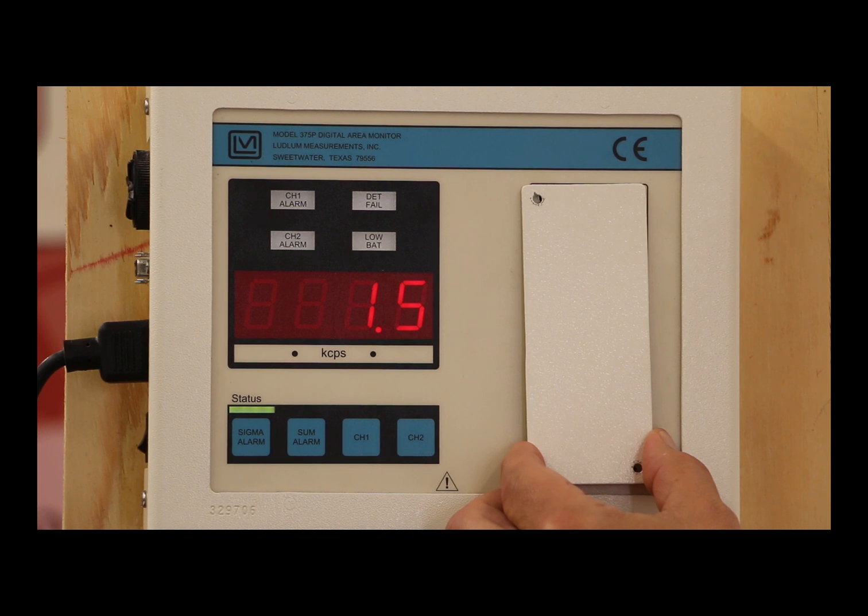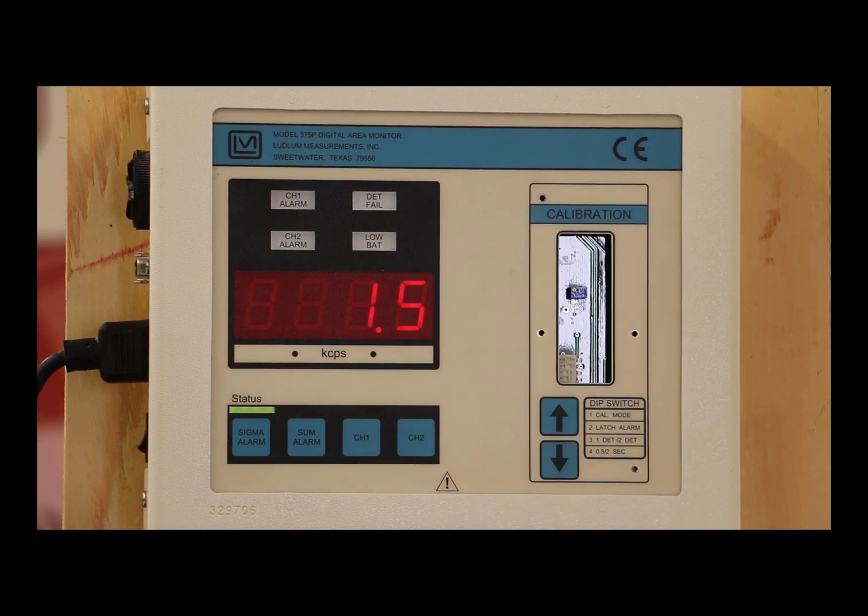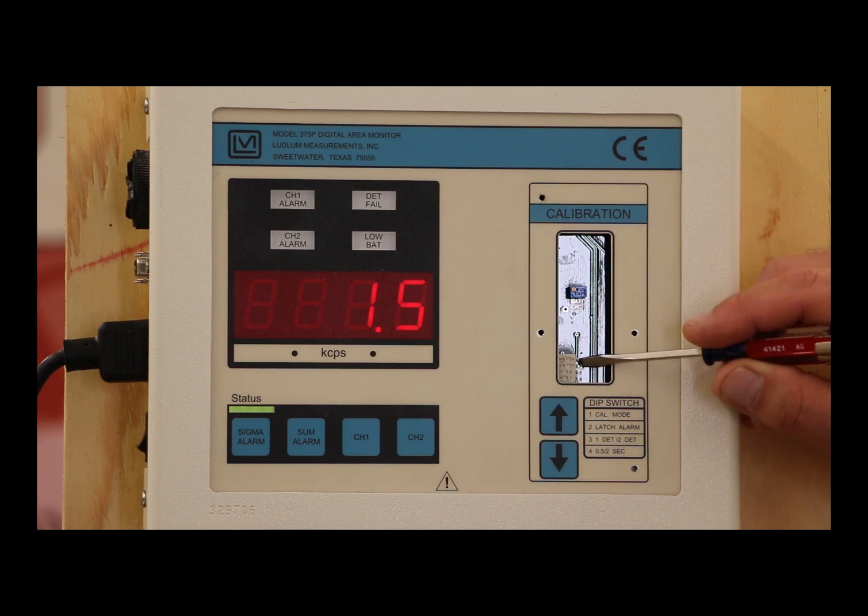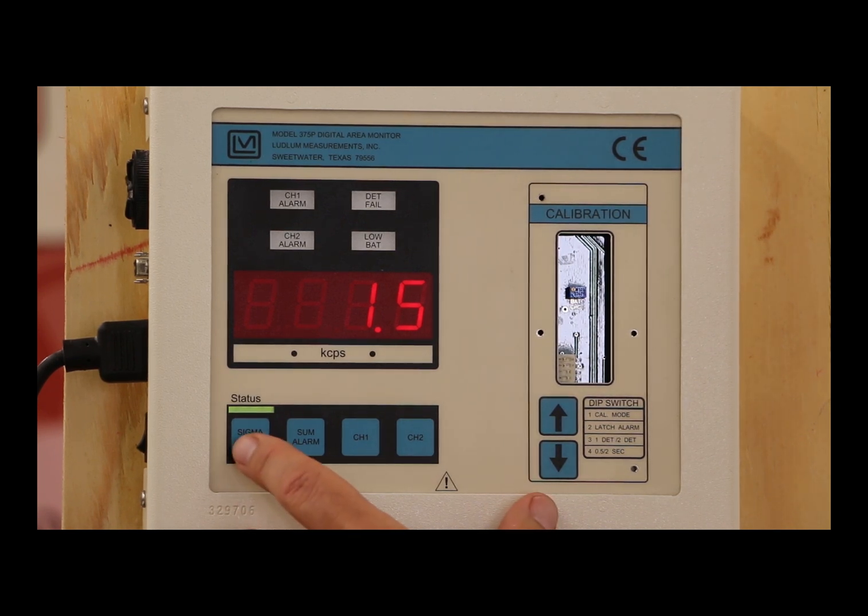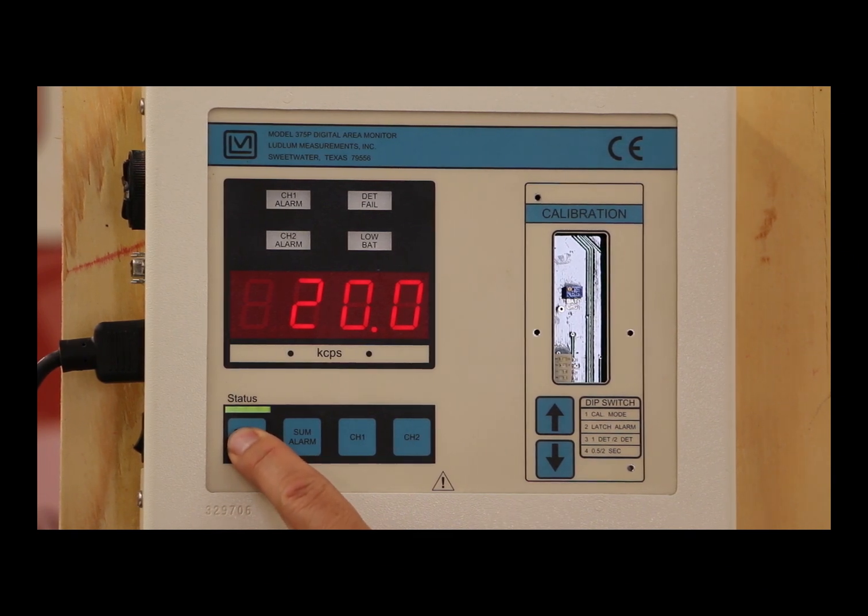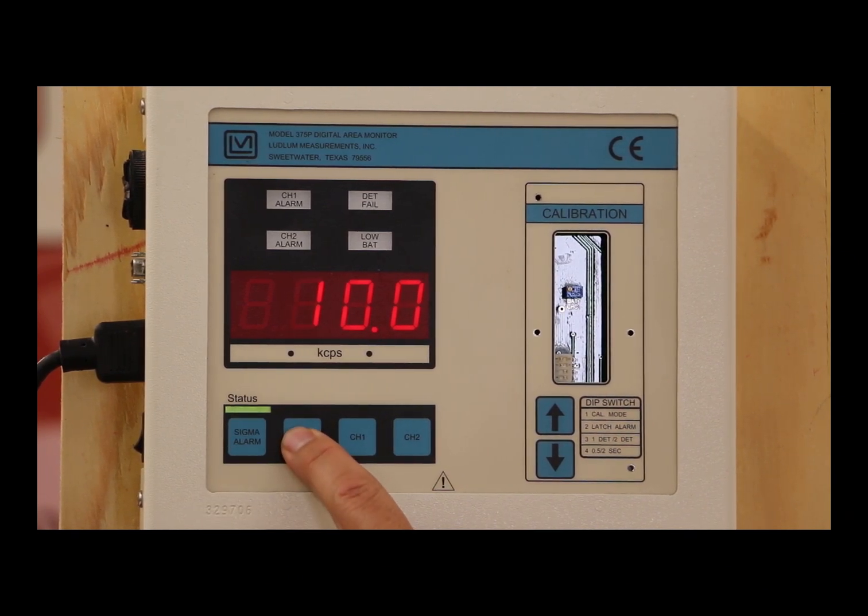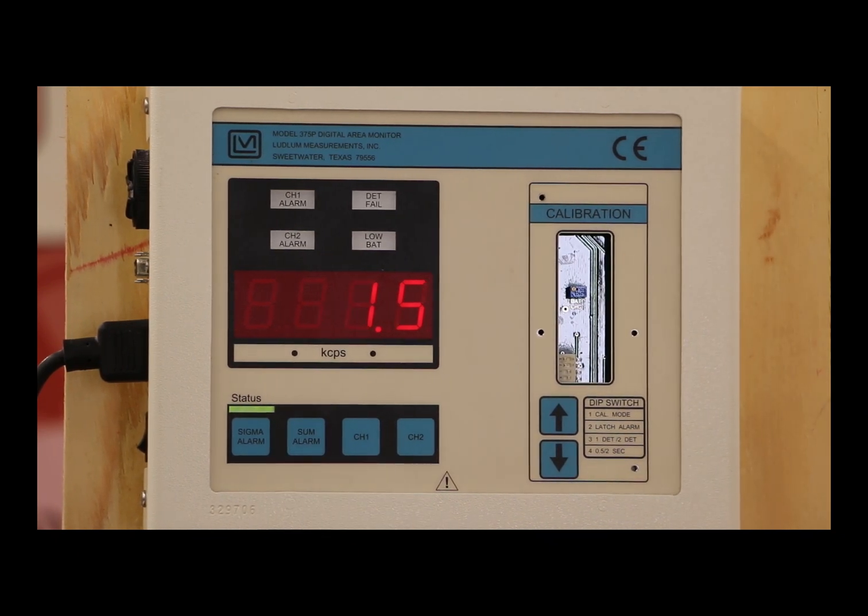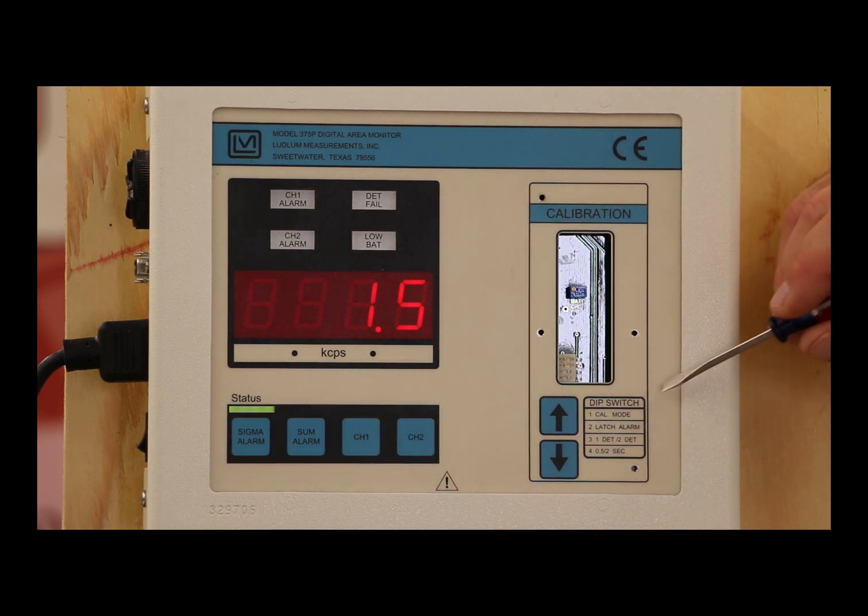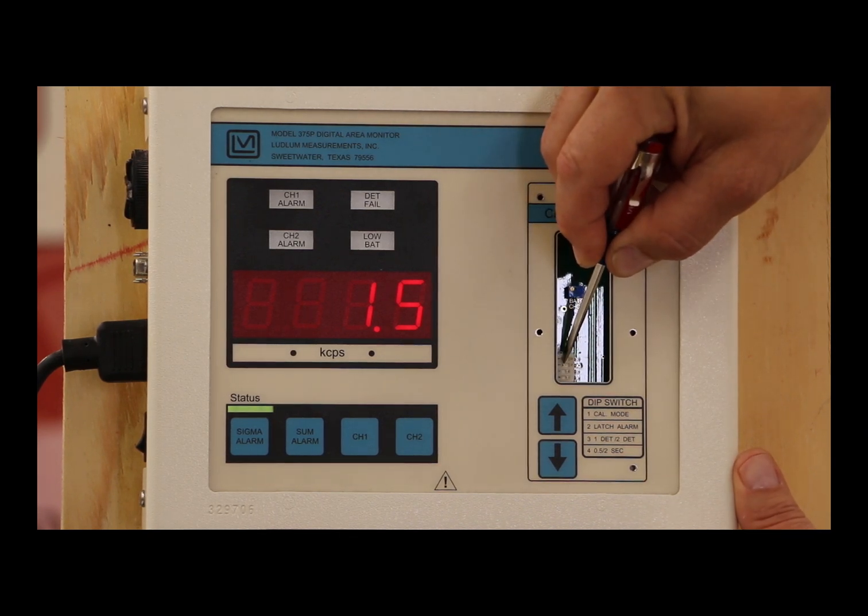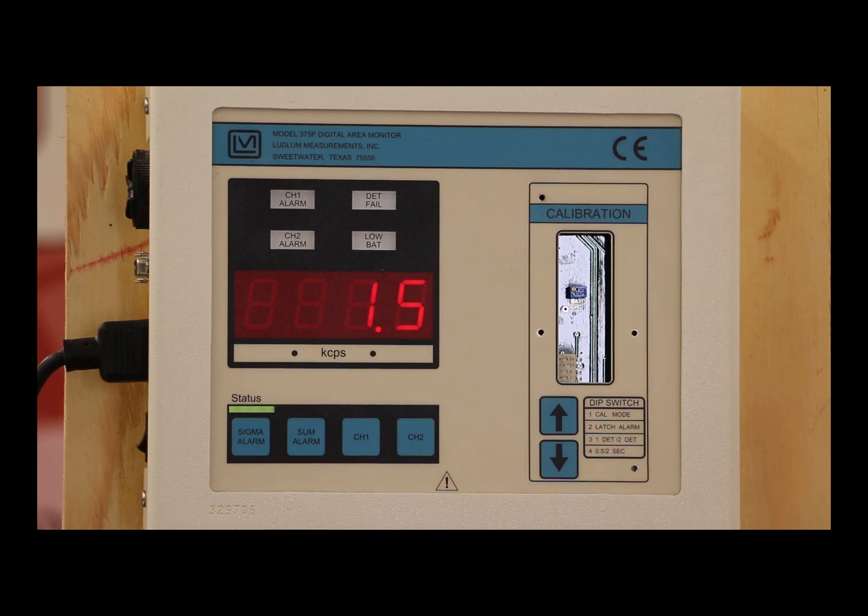Now let's talk about the setup of the 375P. If I remove the calibration cover, you see that we've got four different dip switches, and two arrows to move the parameter numbers. I'll show you how to set this up. Because we've got two alarms in there. As you remember, we have the sigma alarm, currently at 20, and the sum alarm, which is set at 10,000 counts per second. We have four different dip switches here. As you can see, we label them here. The first one is the CAL mode. Right now, the instrument is in CAL lock. So I can't change any of the parameters. In order to change the parameters, I need to move that switch over to the right. And now I can change the parameters.